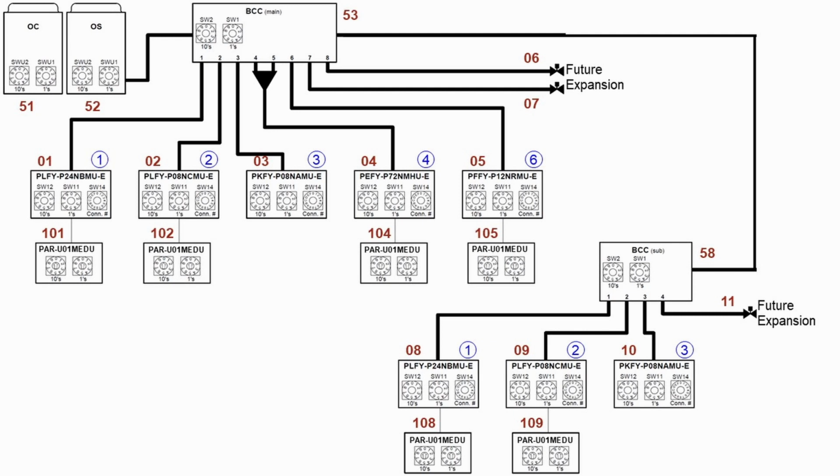Indoor unit number 4 is attached to ports 4 and 5. There is a twinning kit. Each BC controller port will give a maximum of 54,000 BTUs. If the indoor unit you're using is larger than 54,000 BTUs, it must be connected to 2 ports. When you're connected to 2 ports, you set the port setting to the lower of the 2. In this case, when the BC controller opens port 4, it knows that it needs to also open port 5 because the indoor unit that's calling is a 72,000 BTU. Indoor unit number 5 is attached to port 6.